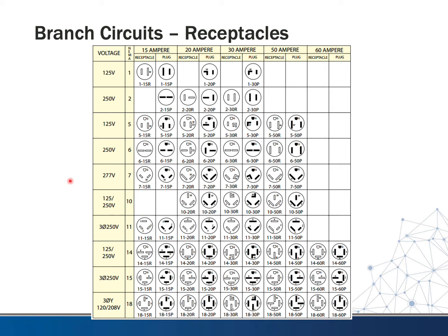Some of these might look familiar. Probably one of the more familiar ones is the NEMA 5-15R. We get that number from the 5, which corresponds with the voltage column, and 15 is the amperage rating. The R stands for receptacle — so if you say 5-15R, I know you need the receptacle. If you say 5-15P, you need the plug, which is the cord cap that goes into that receptacle.